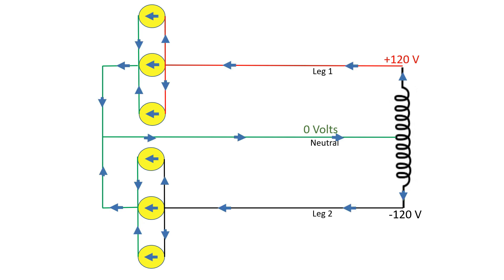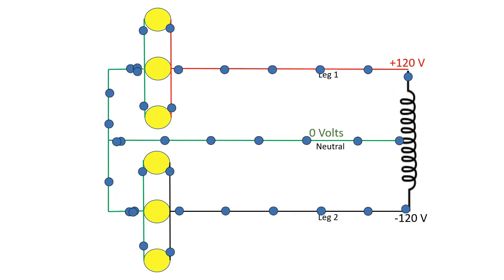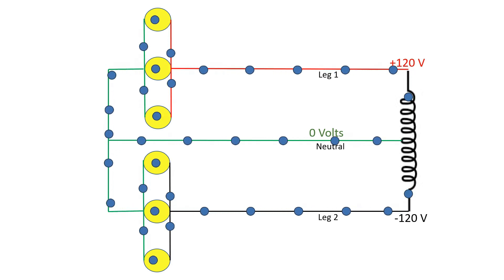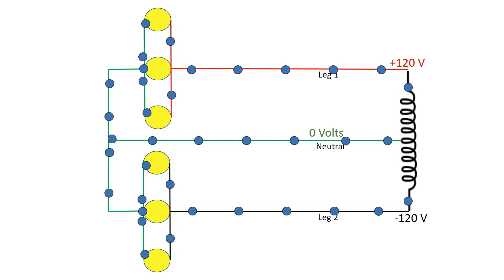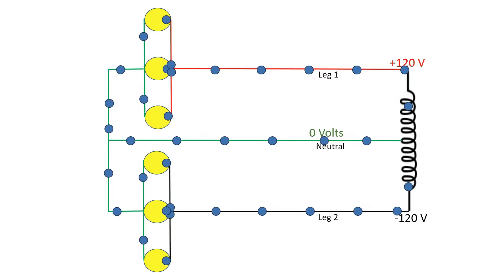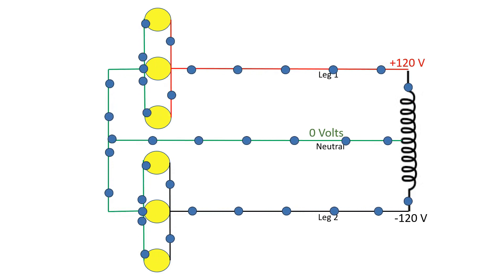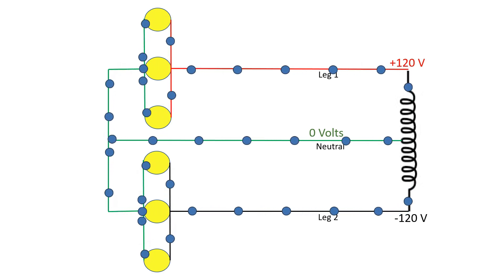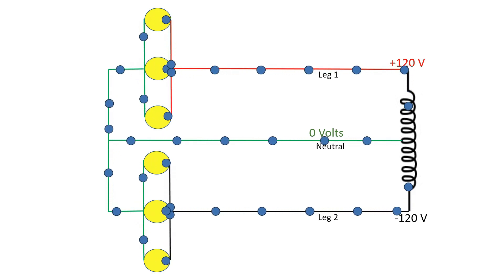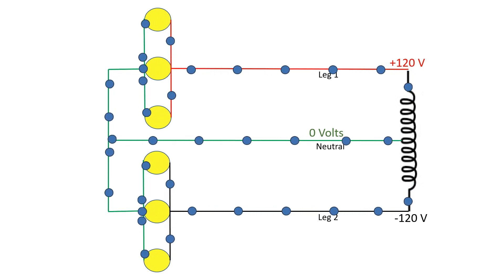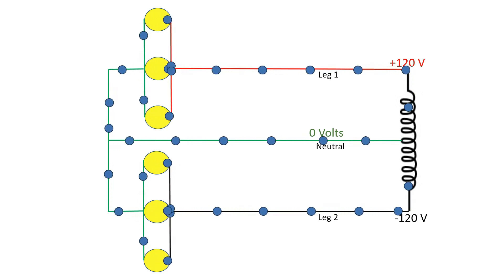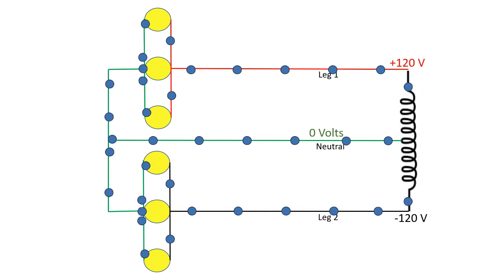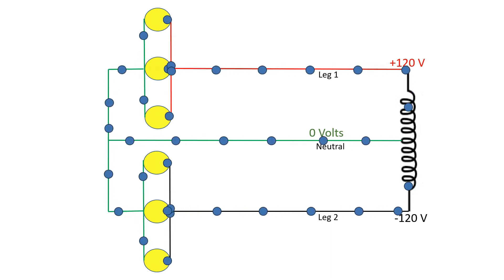The three lights on each leg are in parallel with each other, which means they are all at the same voltage. I'm going to rotate these lights so you can see they're definitely in parallel — this is the exact same circuit with the lights simply rotated vertically instead of horizontally. These arrows show how the electricity flows. One thing I'll interject here is that when you have a completely balanced load on each leg, you actually will have no current on the neutral wire.